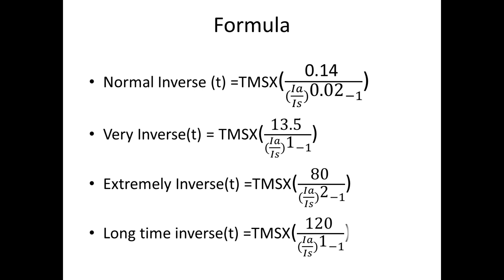Now we are going to see the same overload with these curve settings. I am going to consider normal inverse curve, same current setting, and TMS is 0.8. I am going to find the trip time now for this same overload condition.